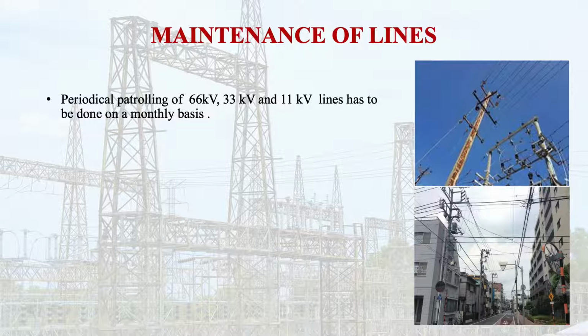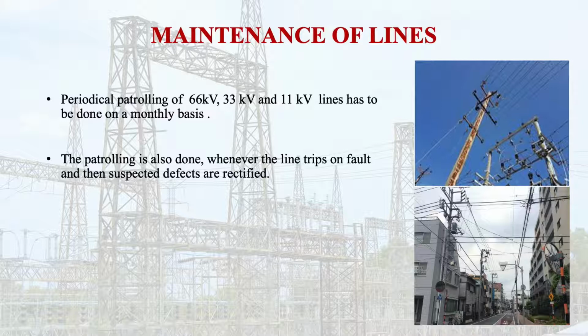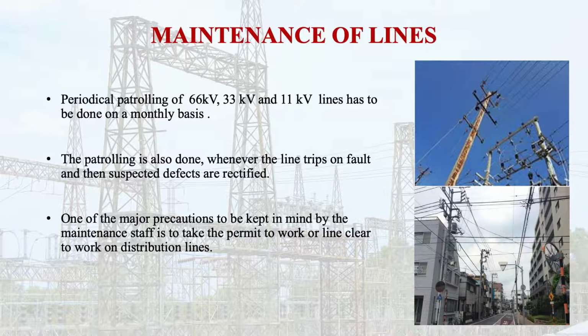Periodical patrolling of 66 kV, 33 kV and 11 kV lines has to be done on a monthly basis. And the patrolling is done whenever the line trips on fault and then suspected defects are rectified. One of the major precautions to be kept in mind by maintenance staff is to take the permit to work or line clear to work on distribution lines. So what is this work permit or permit to work system?